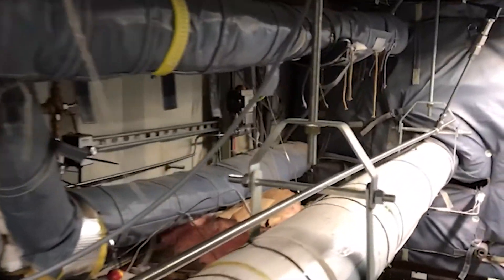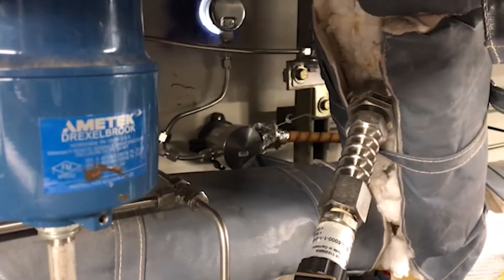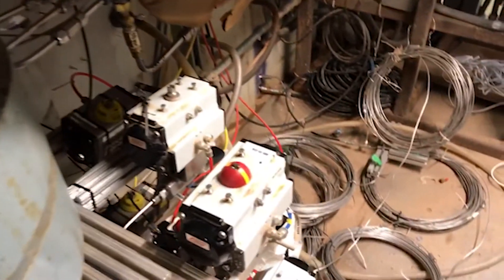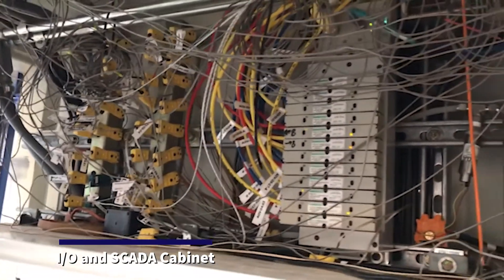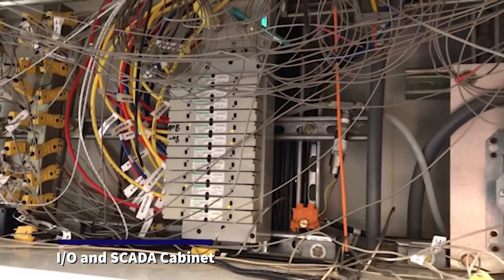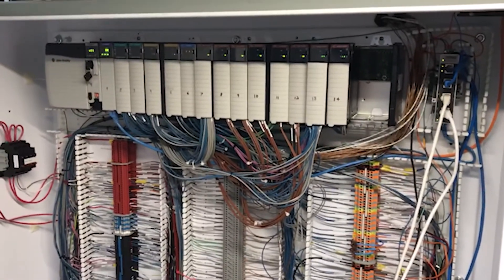After the reaction, the heat is recovered in those heat exchangers. The phases are then separated — the gases are depressurized through a back pressure regulator located behind here, and the liquid gets depressurized through these long capillaries, these coils, that we can see here on the ground, and then discharged at atmospheric pressure. Up here are connections for the thermocouples and the pneumatic valves. This cabinet has all the electrical connections for all the sensors and actuators, with the controllers at the top.